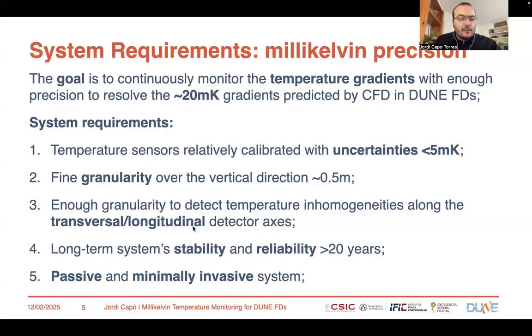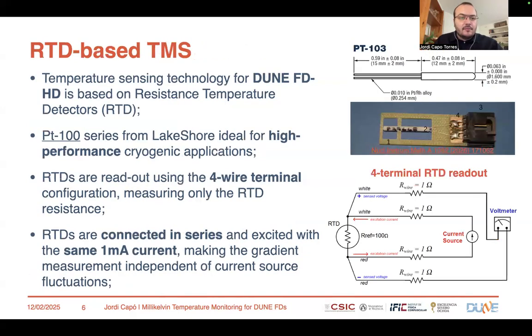The system has to perform stably and reliably over more than 20 years, which is the DUNE expected operation time, and it has to be passive and minimally invasive with respect to other detector systems of the TPC. So, to pursue that, we have developed an intense R&D based on two technologies. The first one is the utilization of the RTDs, which stand for resistance temperature detectors.